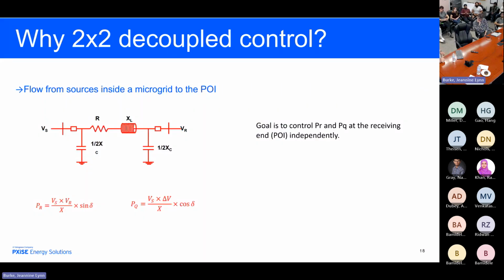This is another simple example. What we're trying to control here is the real and reactive power on the right-hand side of that circuit. By controlling the angle, we can control the voltages to get the real and reactive power flow that we want at the receiving end. So this is why we are strongly urging industry to adopt a 2x2 decoupled controller with time delay compensation.